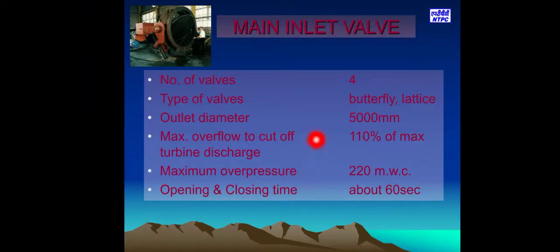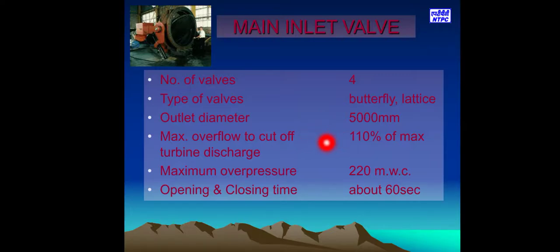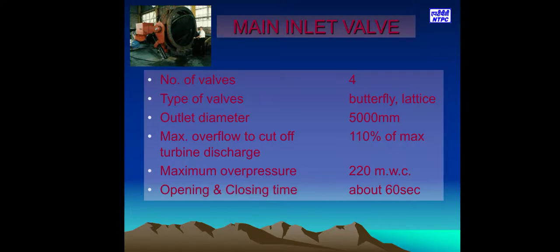Main Inlet Valve: Number of valves: 4. Type of valves: Butterfly. Outlet diameter: 5000 mm. Maximum overflow to cut off turbine discharge: 110% of maximum. Maximum overpressure: 220 MWC. Opening and closing time: approximately 60 seconds.